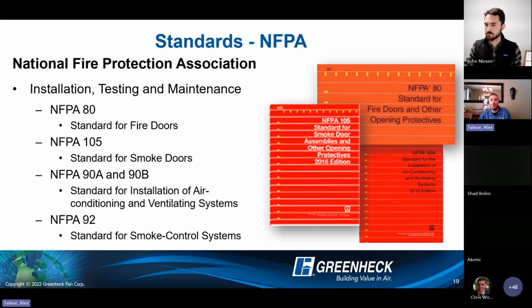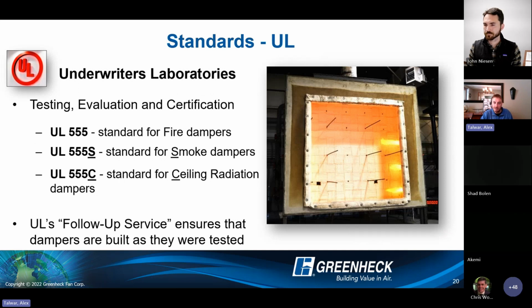You notice this is fire doors, but dampers are also included in these standards as well. Not going to spend too much time on here right now. UL test standards, you can see there we have a separate one for fire, smoke, and ceiling radiation dampers. And then UL also does something called a follow-up service program, essentially a factory inspection, making sure that we are building the products the same way that they are approved and were qualified when they were tested. So that's certainly a very important aspect.